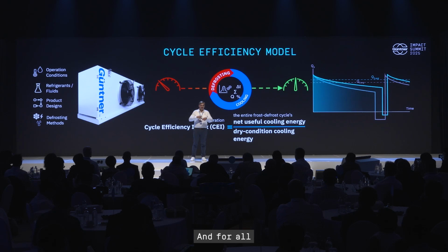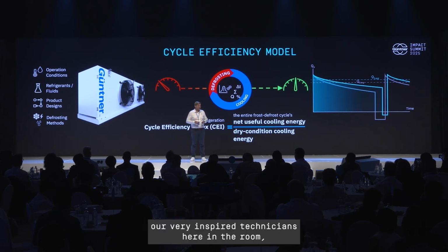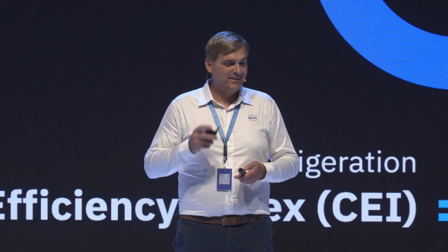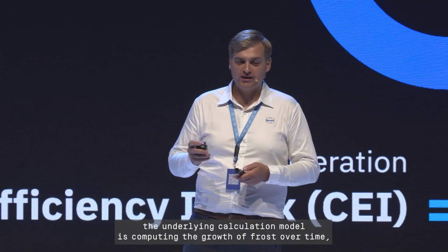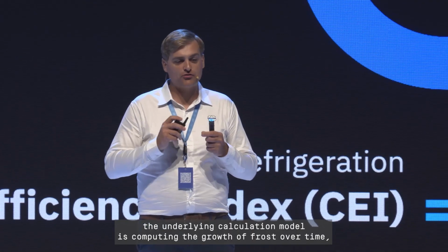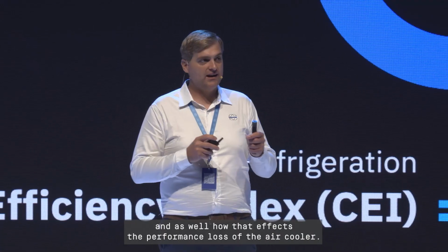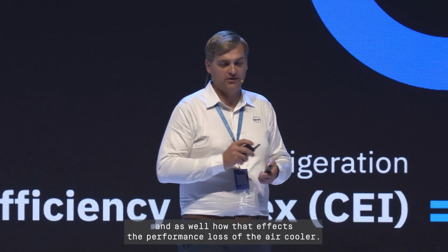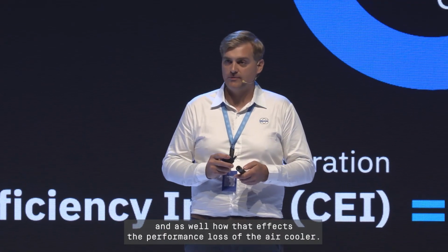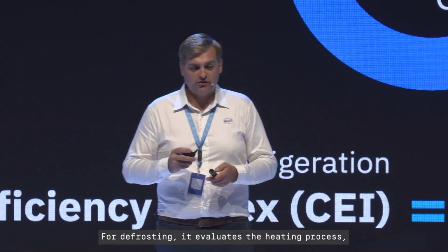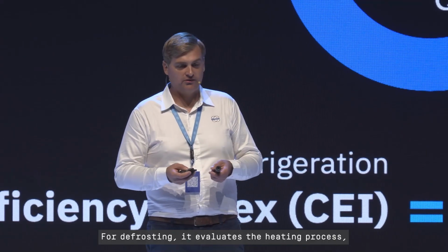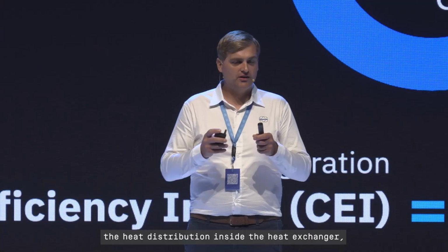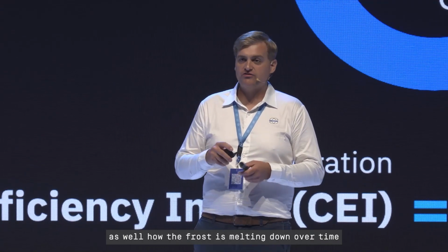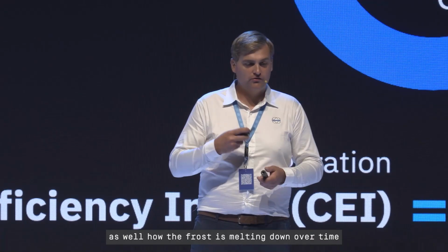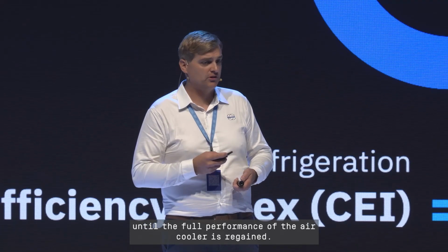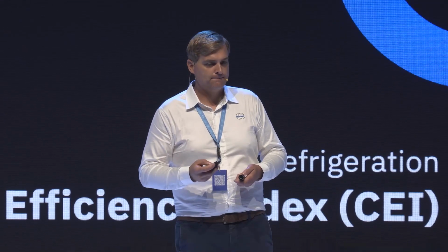And for all our very inspired technicians here in the room, the underlying calculation model computes the growth of frost over time and how that affects the performance loss of the air cooler. For defrosting, it evaluates the heating process, the heat distribution inside the heat exchanger, as well as how the frost melts down over time until the full performance of the air cooler is regained.